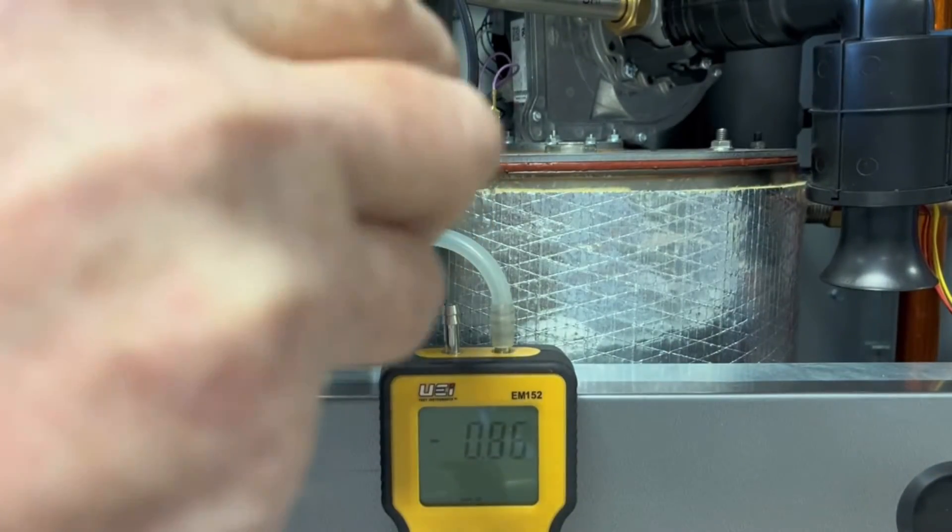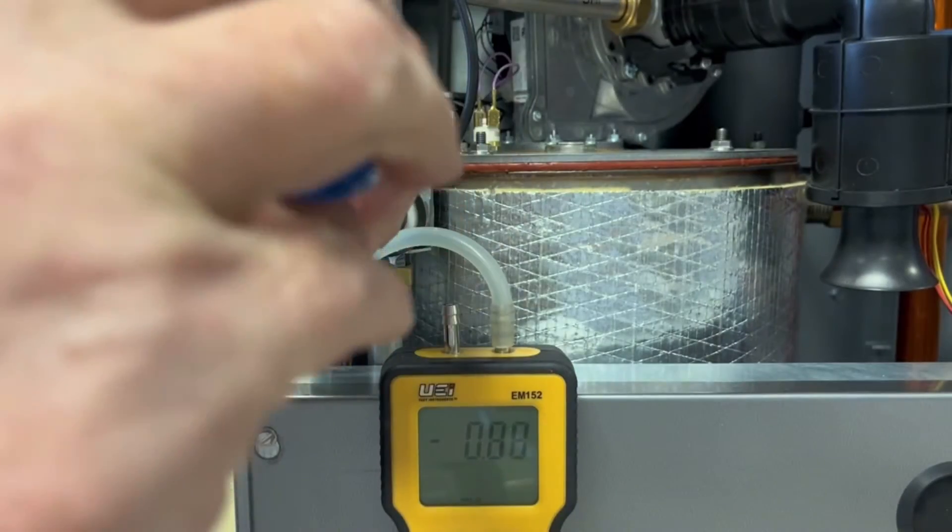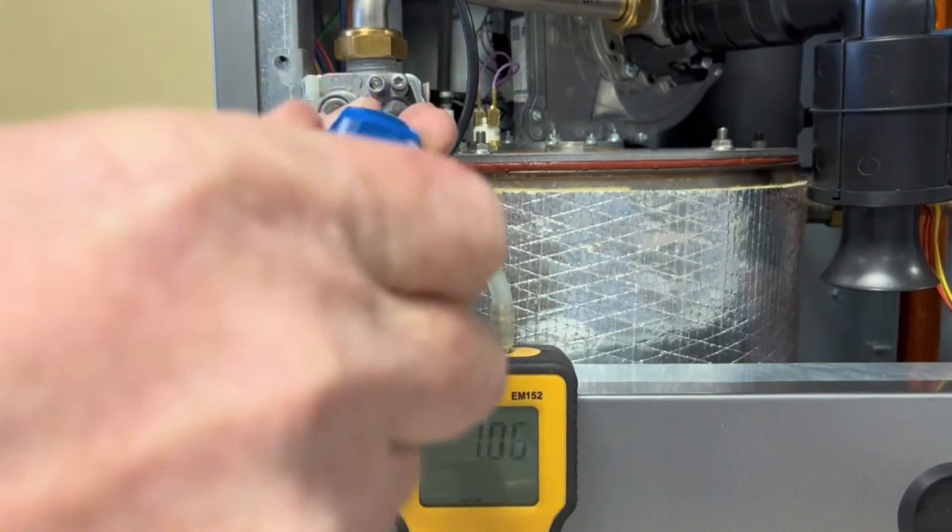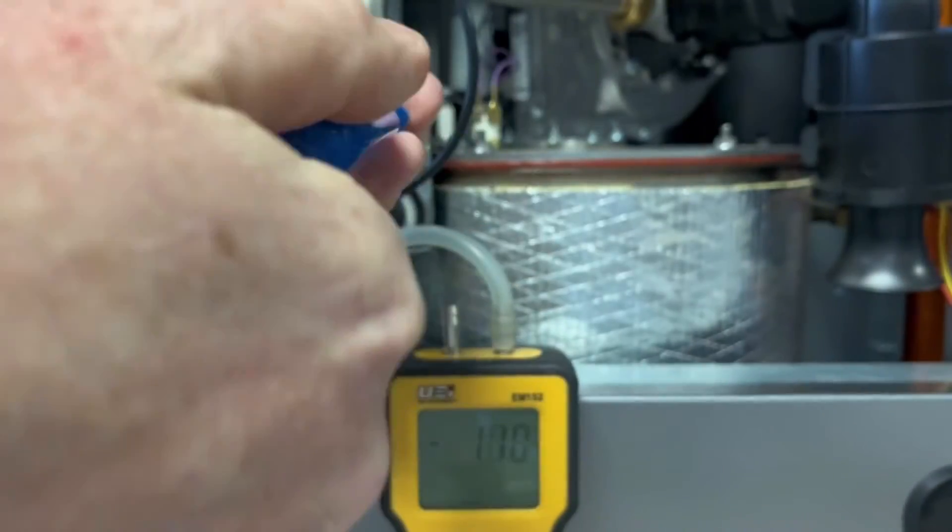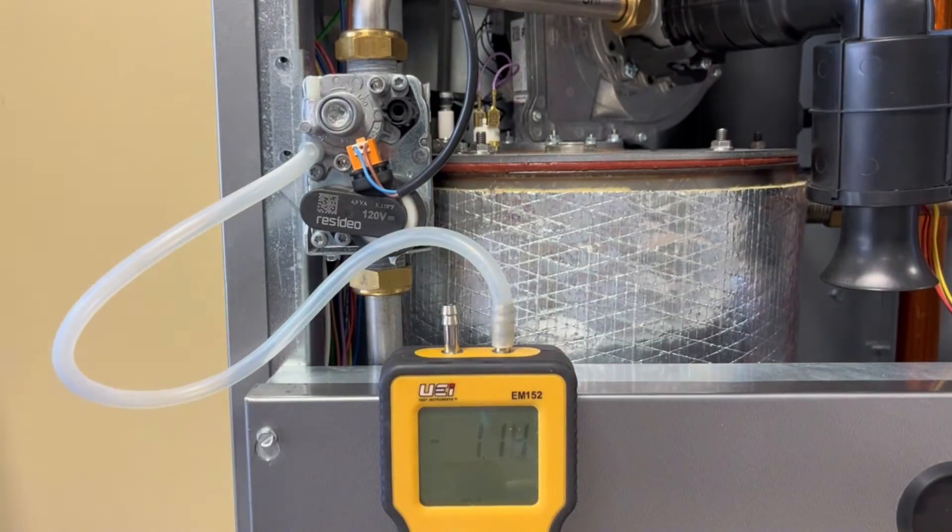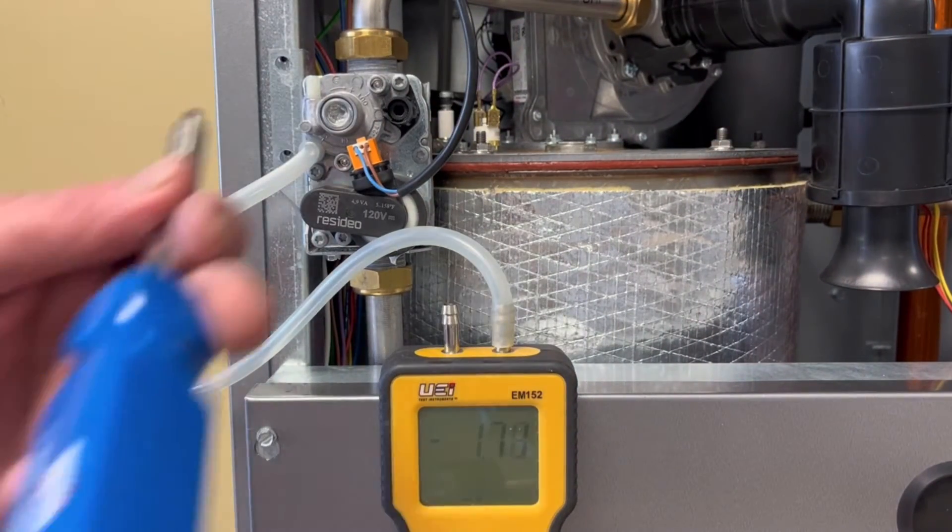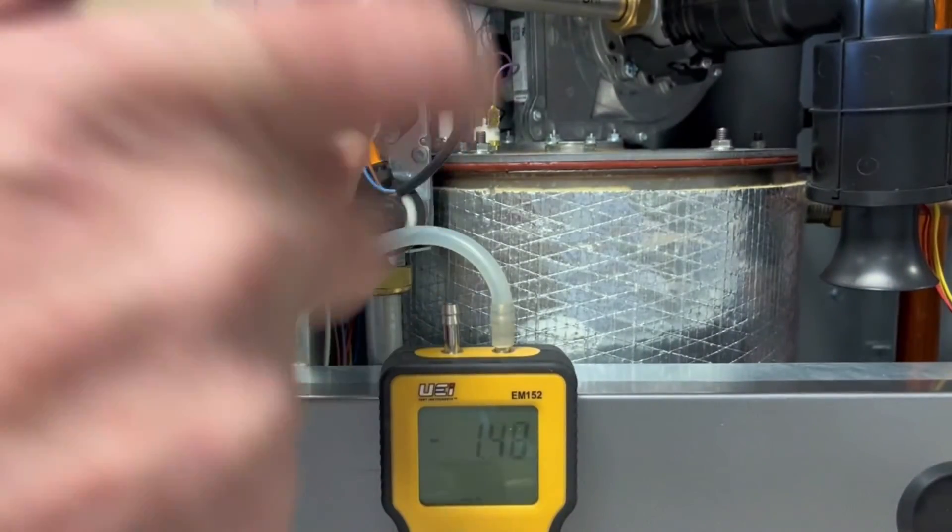Now carefully turn the screw counterclockwise four complete revolutions. This should bring the valve to an approximate factory setting. Now you can complete your high fire combustion analysis and set the valve for the specifications in the manual.